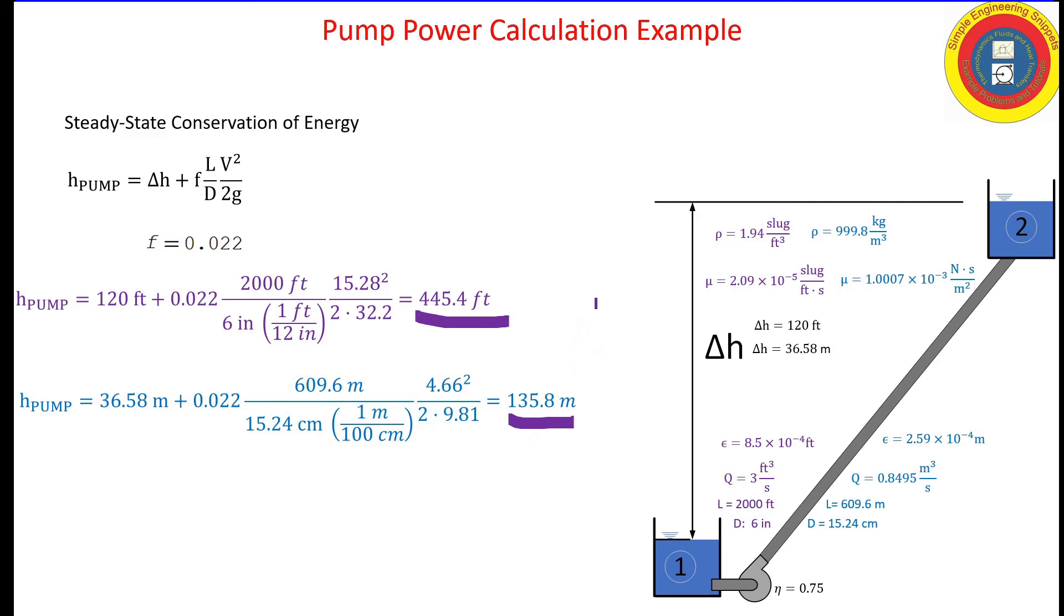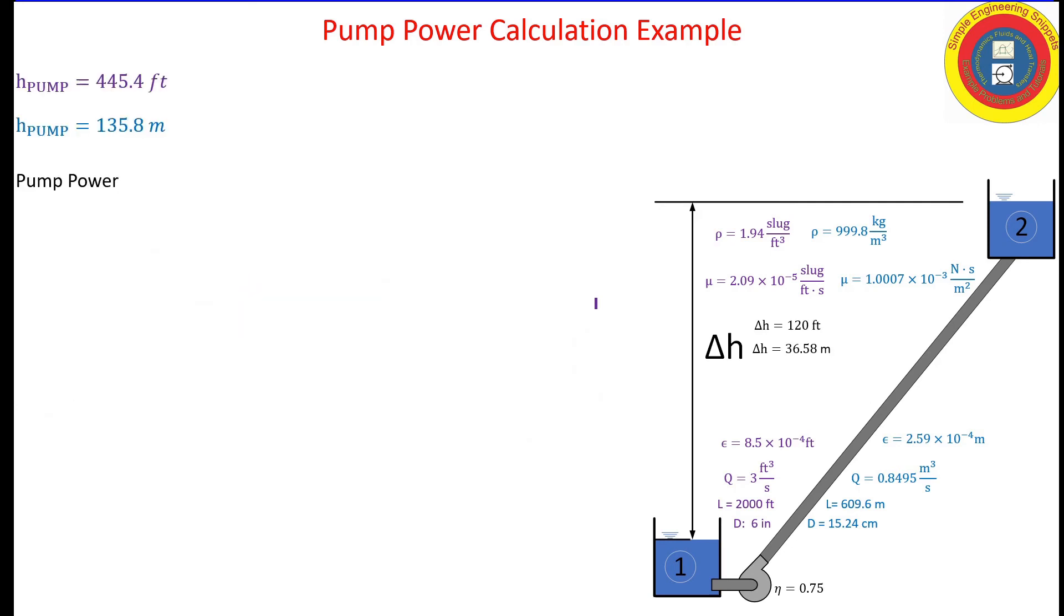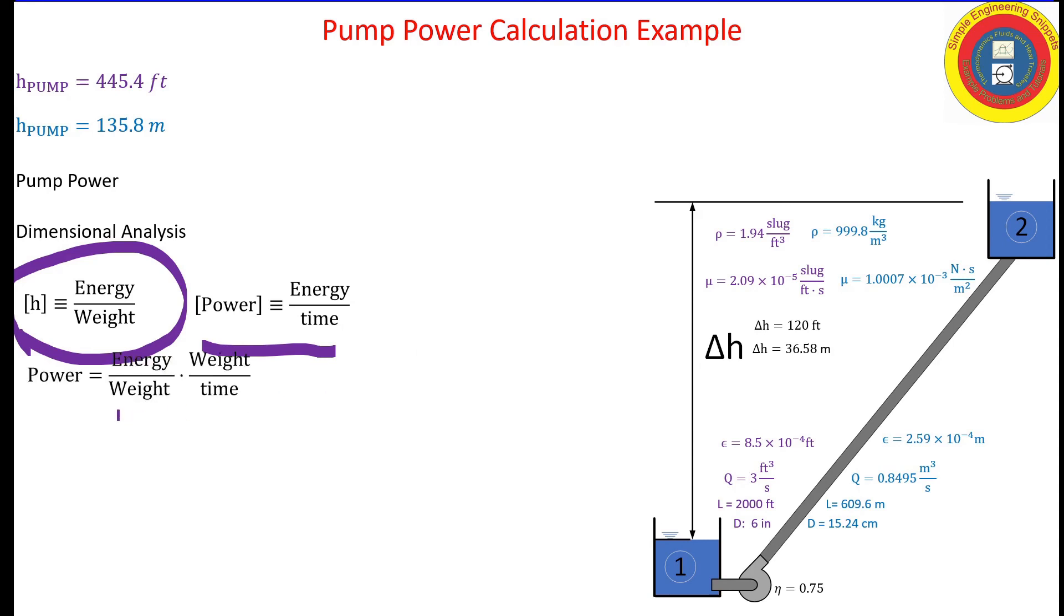We weren't looking for the pump head. We were looking for the pump power. So how do we obtain that? One way is just looking at dimensional analysis. As we stated earlier, my pump head is energy per weight. We know power is energy per time. So to obtain power from pump head, I take the energy per weight and multiply it by weight per time.